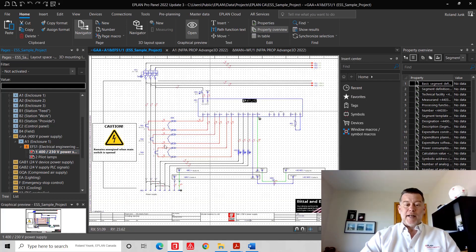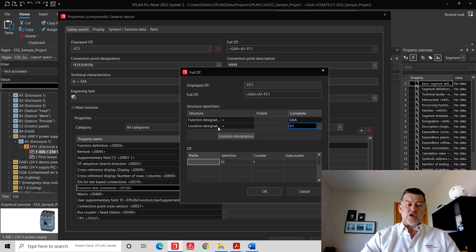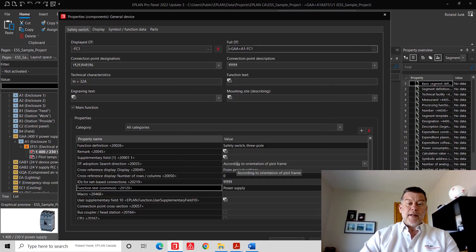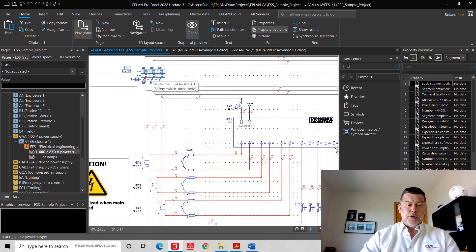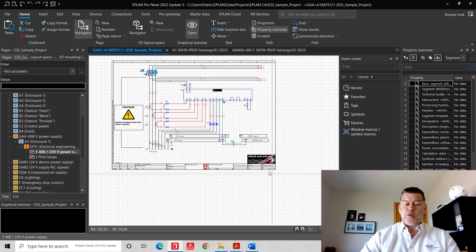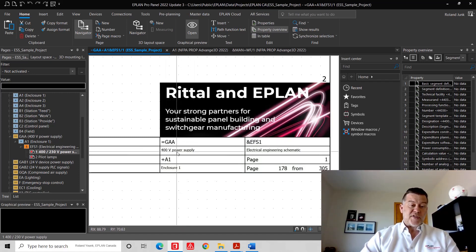The idea is that every single component can have three different aspects to define it. To define a specific component — like this safety switch here — we can assign three different things: first, the physical location where the component is; second, what general functional designation we can assign it to; and third, the identifier that follows certain rules. The device itself only shows the last item, like FC1, but the rest of the information comes from this section of the page, where we specify that equal GAA represents 400-volt power supply and plus A1 is enclosure one.